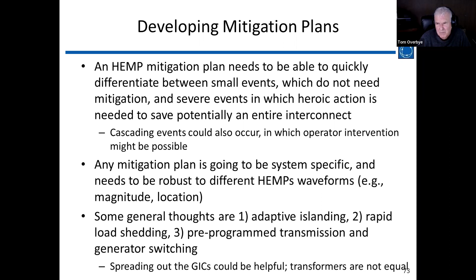We might want to try to spread out the GICs if it's a more concentrated footprint. Then spreading out the GICs might be more useful, and that could be done by opening certain generators that removes path to ground. It could be opening transformers between, say, in the 2000 bus case, we would open 500 to 161 kV transformers, or sometimes 161 to 115, and that seemed to help.